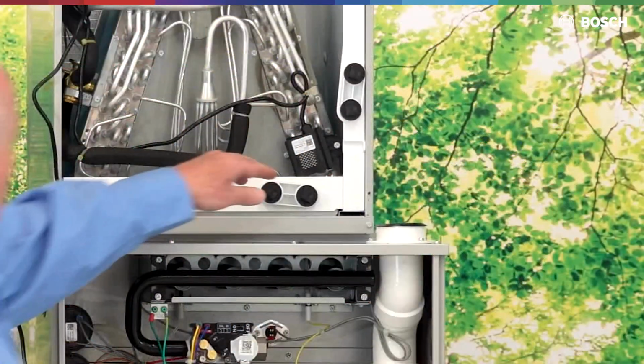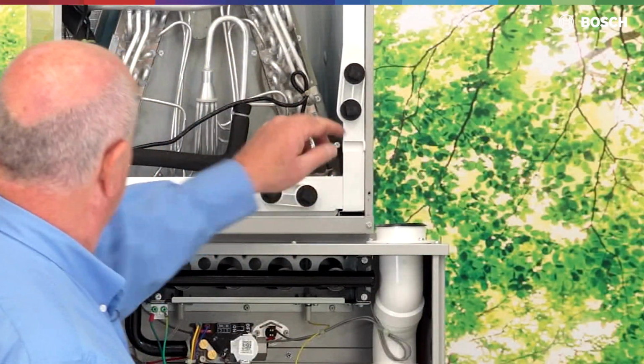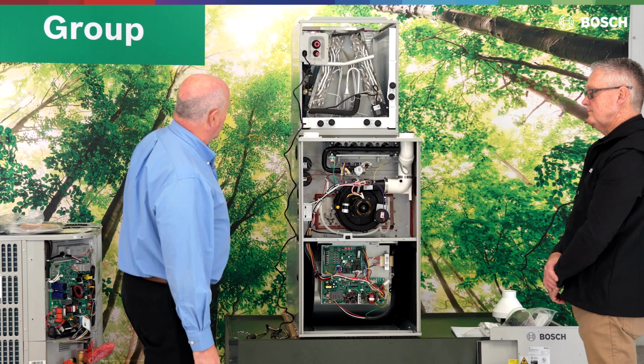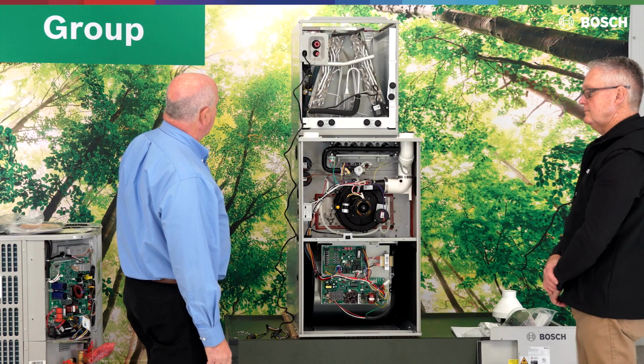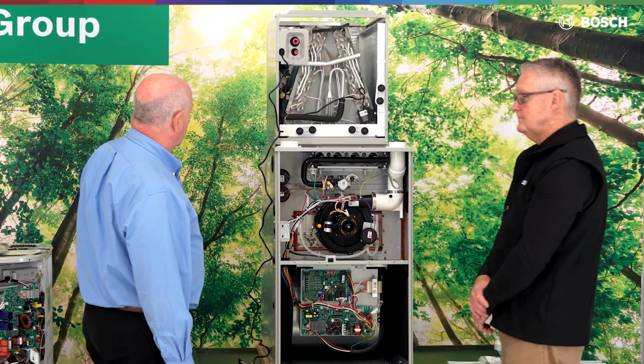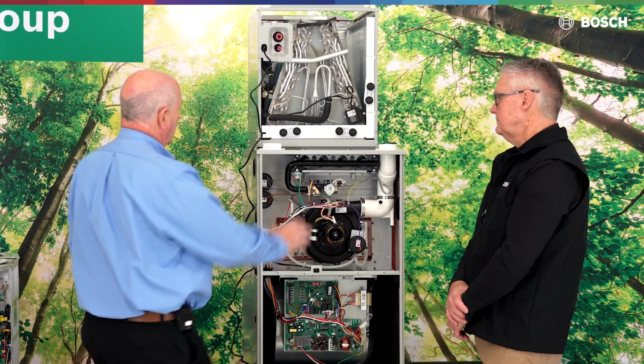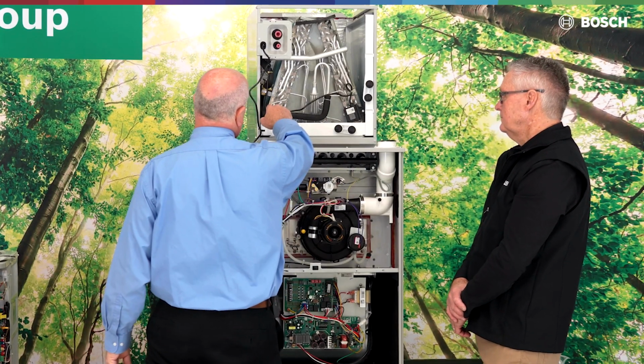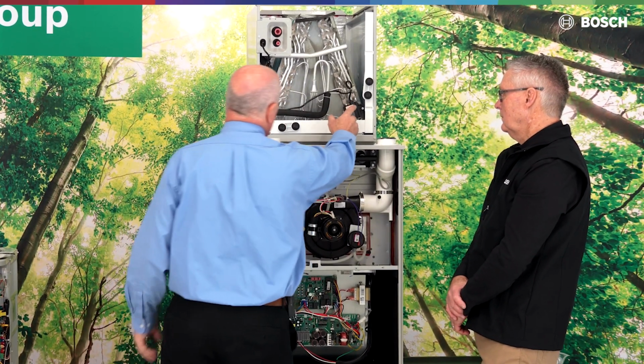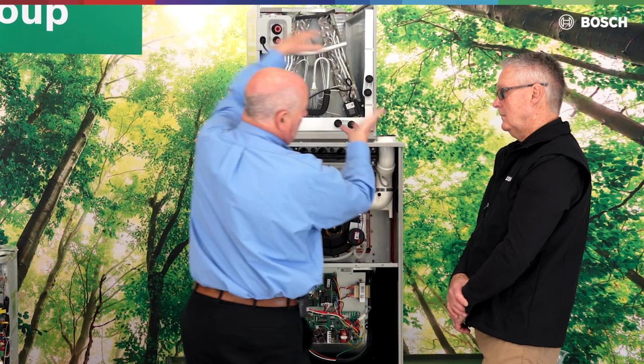So we have our A2L sensor located right here, and that A2L sensor is good to go. If we turn this from a left-hand return to a right-hand return, we'd have to move our sensor to this side of the coil. We want this sensor on the bottom of the coil if we're going horizontal.